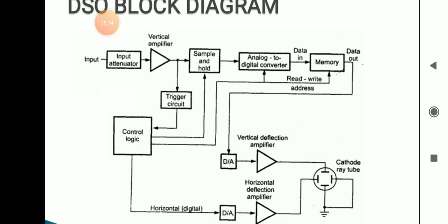So for single channel you can use 1024, two channels you can use 2048, and four channels you can use 4096. It has some memory capacity, storage capacity. And the next point, the selection of sampling rate and the memory size depends on the type of waveform being recorded.